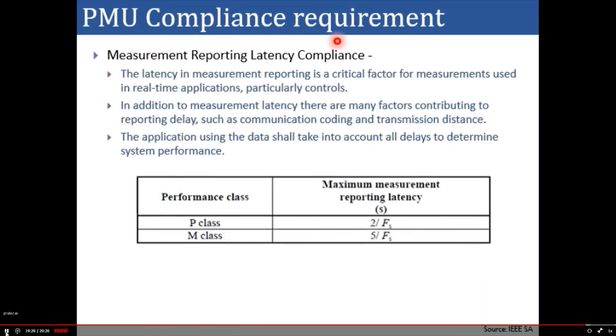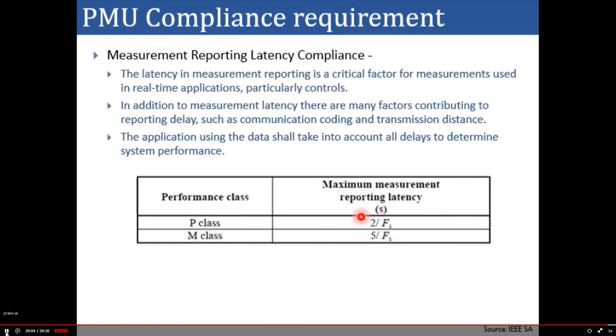For PMU compliance with respect to latency: latency in measurement reporting is a critical factor for real-time applications, particularly in controls. In addition to measurement latency, factors such as communication coding and transmission distance contribute to reporting delays, and applications must account for all these delays. For P class, the maximum delay is 2/FS (where FS is the frame reporting rate). For M class, the maximum delay is 5/FS.